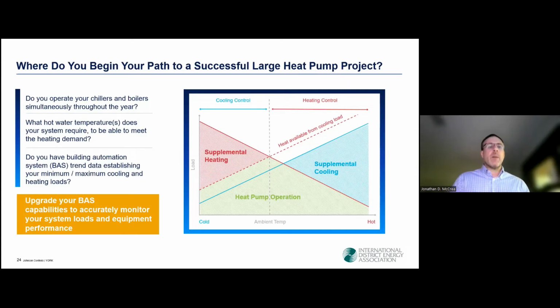The next step beyond that, and it's a really critical one, is to get a handle on what your loads are. So you're going to want to build a really good load profile. The first thing I would go to there is your building automation system.